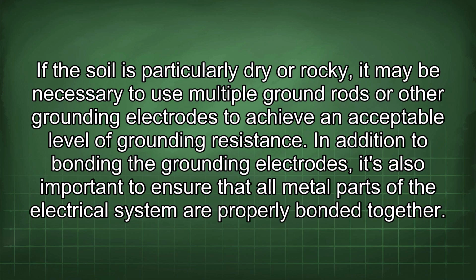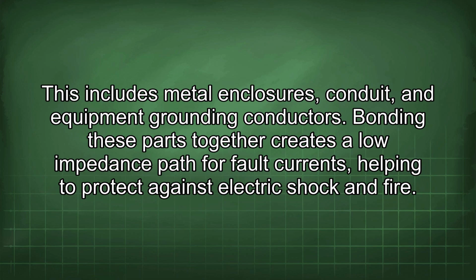In addition to bonding the grounding electrodes, it's also important to ensure that all metal parts of the electrical system are properly bonded together. This includes metal enclosures, conduit, and equipment grounding conductors. Bonding these parts together creates a low impedance path for fault currents, helping to protect against electric shock and fire.